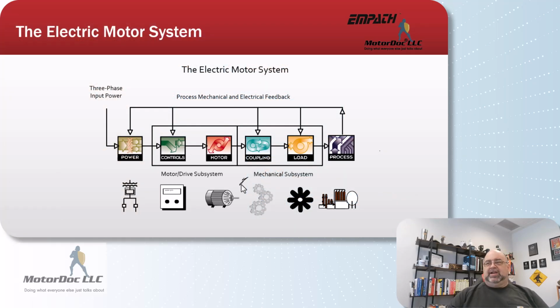So, electric machine system. Now, if I'm talking about electrical signature analysis, it involves taking data between the controls and the motor and taking voltage and current, and voltage data is upstream, current data is downstream from that into the process, et cetera, et cetera. So all of this involves being able to look at the entire system. Current signature analysis could be 1 or 3 phases or 2 phases, whatever is decided by the technology in order to look at the mechanical conditions downstream.